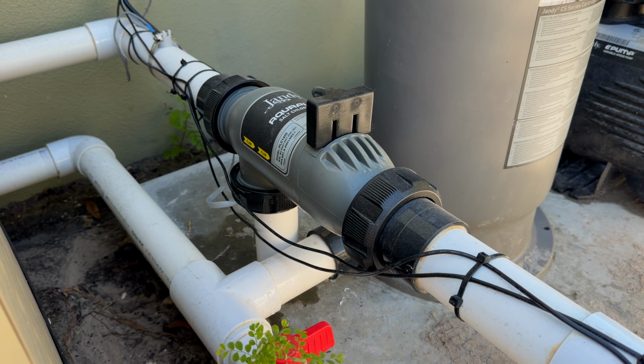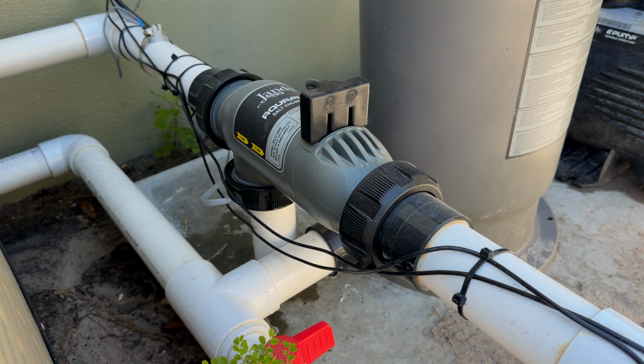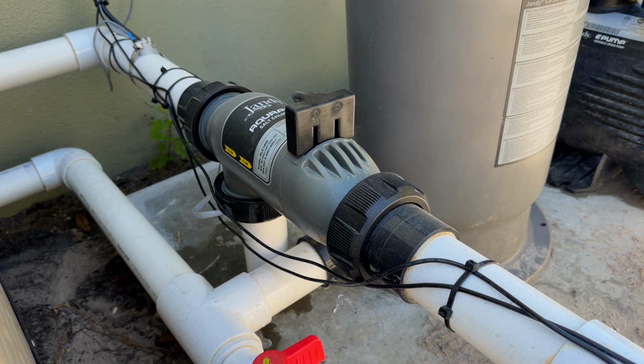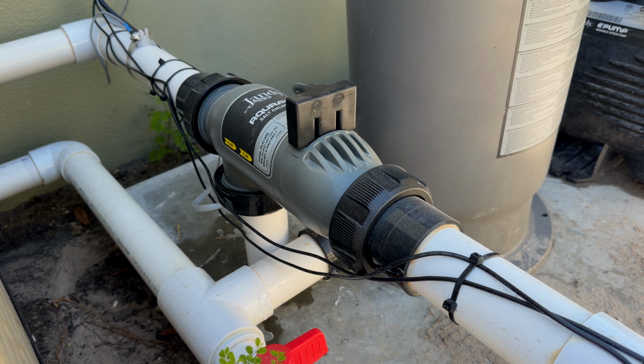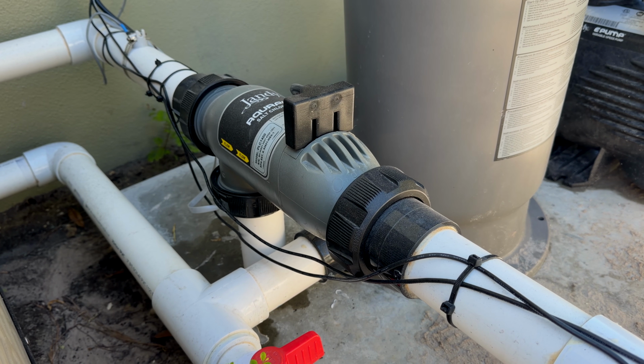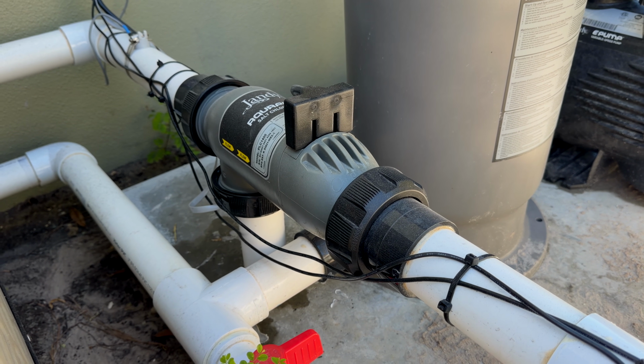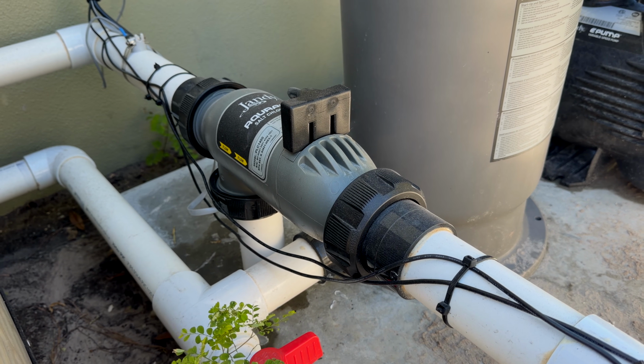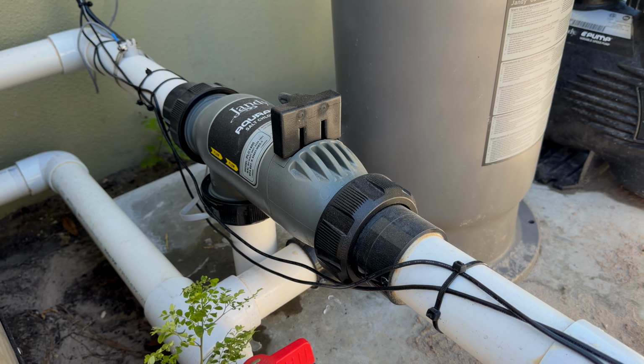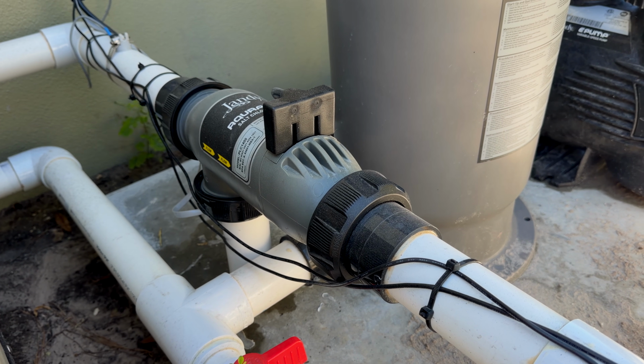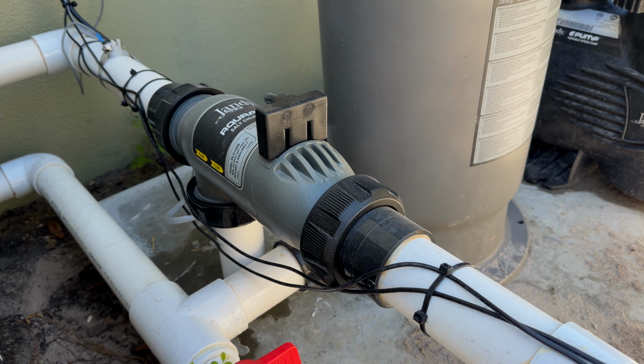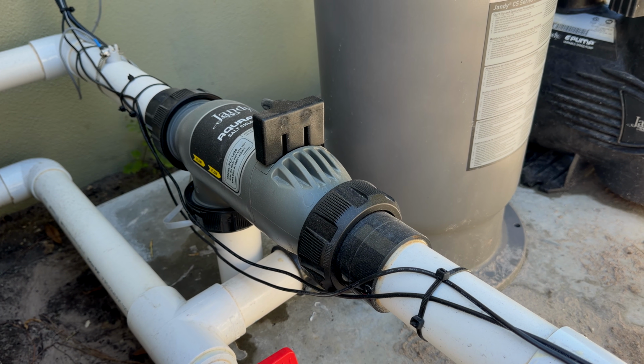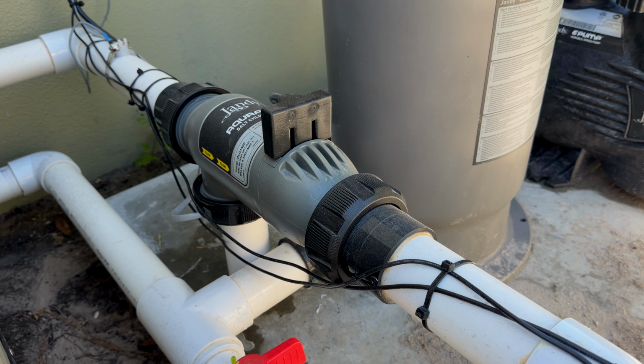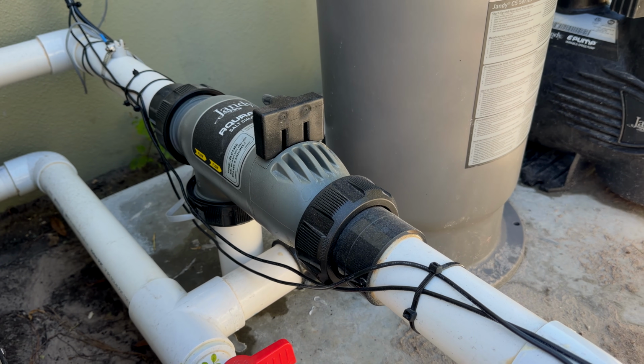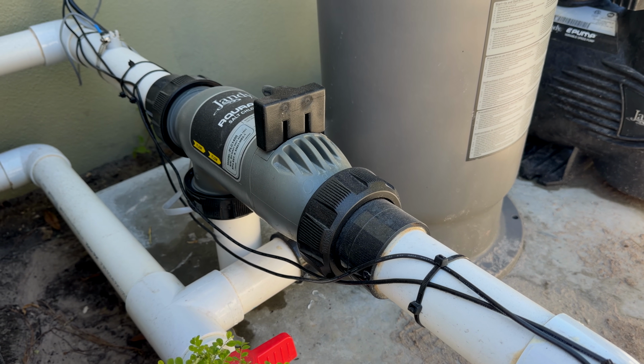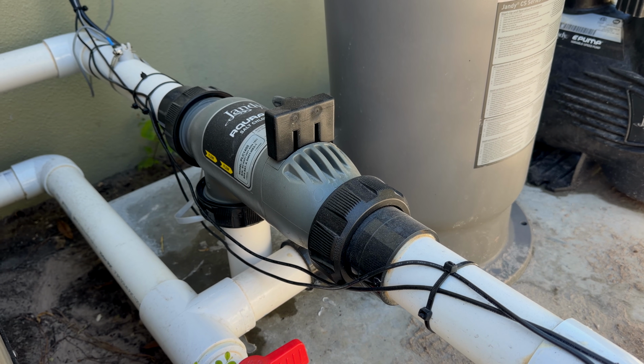The 172 error code is more of a general error code that could be things like calcium buildup or debris on the sensor. The cell could be dirty, so I'm going to check that for calcification, but it could also be a sensor fault. That 180 error code is a sensor fault, and it generally has to deal with the heating elements of the tri-sensor. So we know that needs to be replaced for certain, but just for good measure, I'm going to take the cell out, check it for calcium, and if need be, get that cleaned up as well, in addition to replacing that sensor.